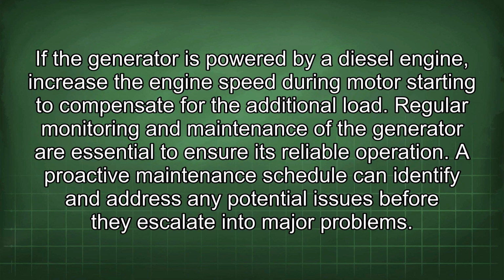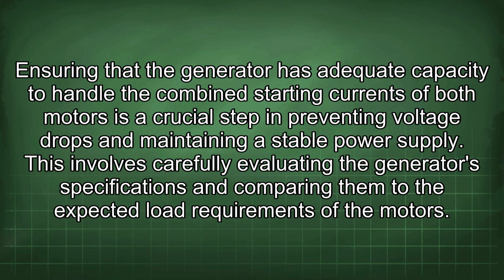If the generator is powered by a diesel engine, increase the engine speed during motor starting to compensate for the additional load. Regular monitoring and maintenance of the generator are essential to ensure its reliable operation. A proactive maintenance schedule can identify and address any potential issues before they escalate into major problems. Ensuring that the generator has adequate capacity to handle the combined starting currents of both motors is a crucial step in preventing voltage drops and maintaining a stable power supply.